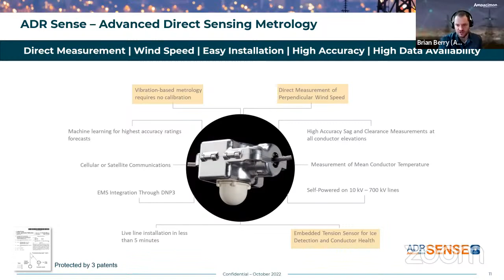And one of the things that we're doing is we're measuring the vibration inside this box. Now you might be sitting there thinking, Brian, you were talking about wind, you're talking about temperature, you're talking about current, and now you're telling me you measure vibration. What on earth are you talking about? That just doesn't make any sense. Well, vibration is at the crux of it, okay? Because when I measure vibration, I can determine sag. And sag is basically how much this line is drooping.